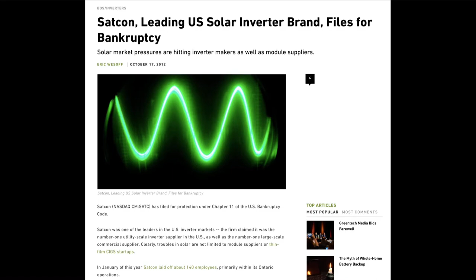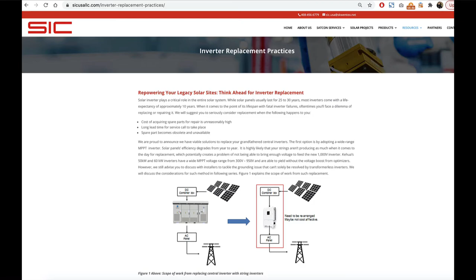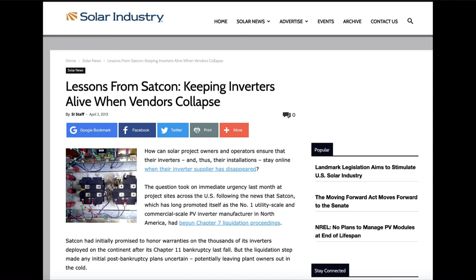So you then have to have monitoring communications protocols that are consistent platform to platform, so you could take one company's equipment, remove it, and put in its place another manufacturer's equipment, and it still talks the same protocols. I think that's ultimately the big challenge with large scale systems - making sure everybody can talk the same language, because we're asking a lot out of our inverters these days. We're operating them in a very advanced way, at non-unity power factors, doing grid support activities, and all this requires a lot of communication. Whereas the old school dumb unity power factor inverter was just plug and chug - that's not the case anymore. So those are the challenges that happen.